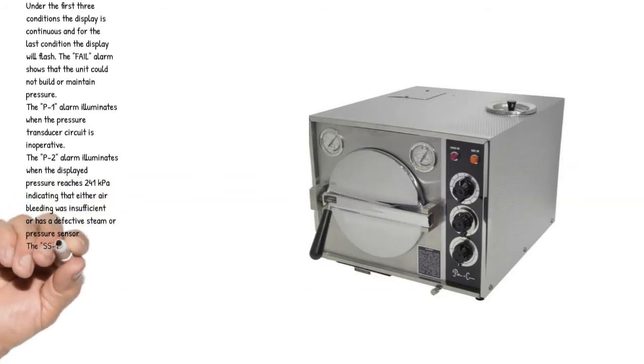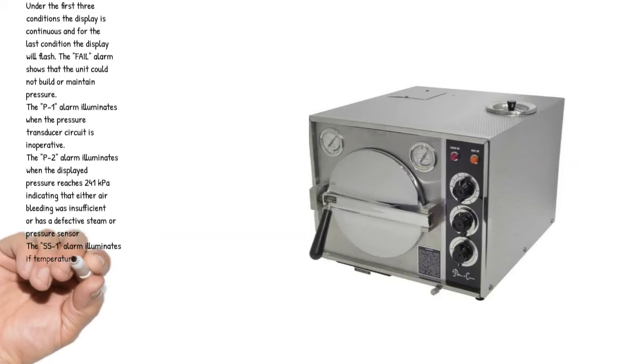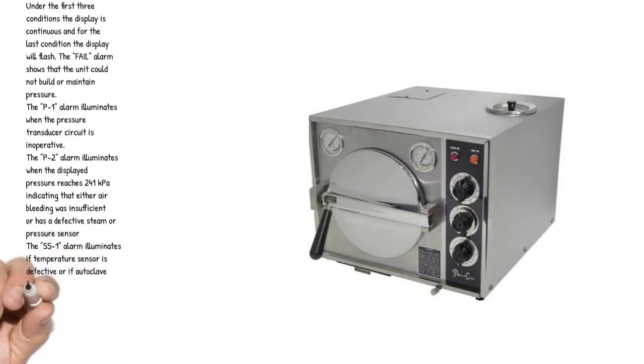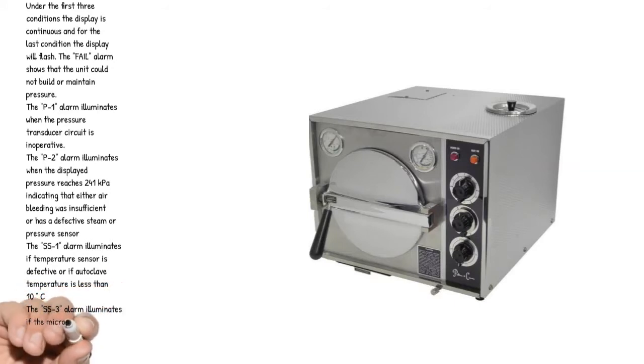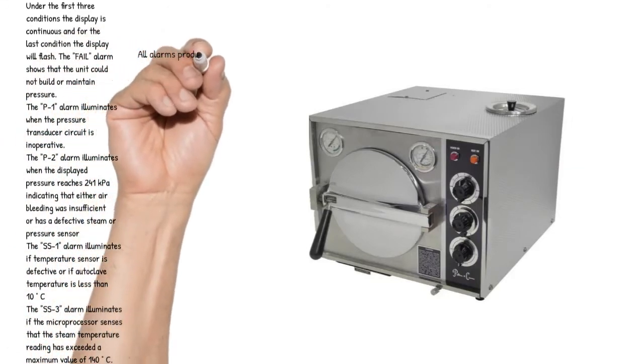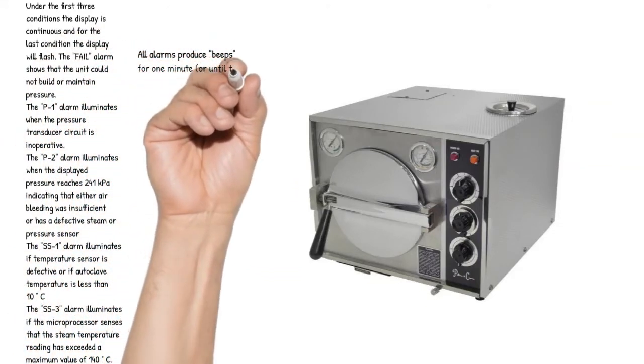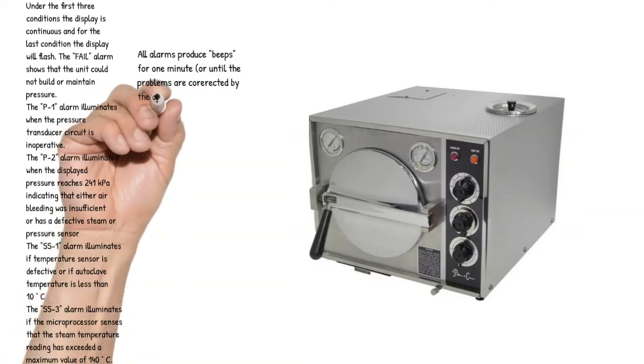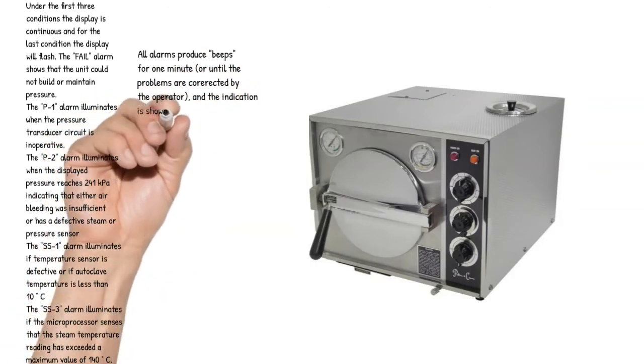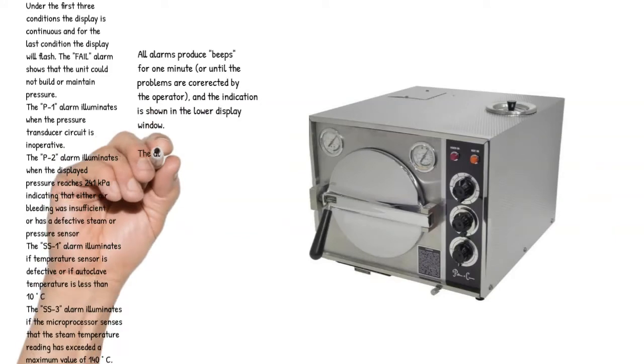The SS1 alarm illuminates if the temperature sensor is defective or if autoclave temperature is less than 10 degrees Celsius. The SS3 alarm illuminates if the microprocessor senses that the steam temperature reading has exceeded a maximum value of 140 degrees Celsius. All alarms produce beeps for 1 minute, or until the problems are corrected by the operator, and the indication is shown in the lower display window.